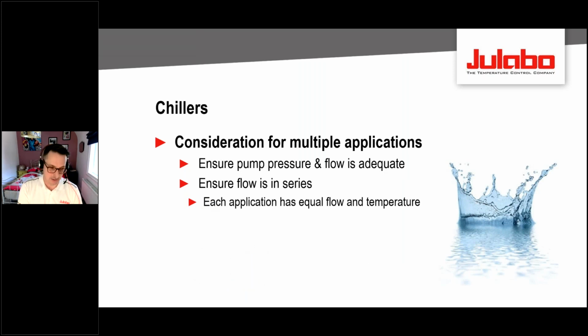That's to ensure that if you had 4 devices in a row, all 4 get cooled water at the same temperature, rather than feeding water from your first device to your second, to your third, to your fourth, so that your 4th device might end up with water at a temperature 10 to 15 degrees higher than your first device.